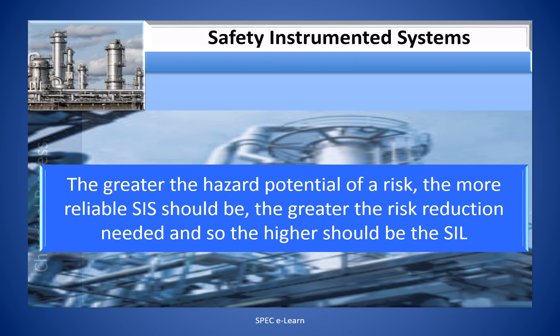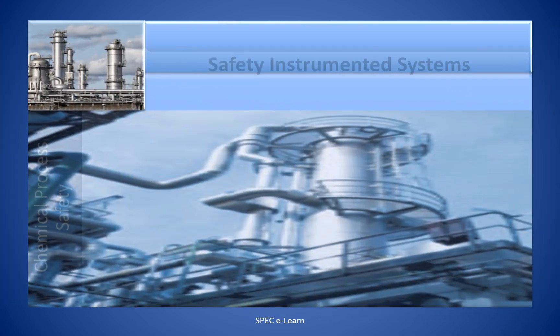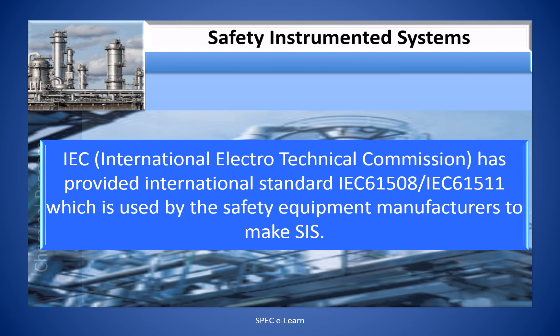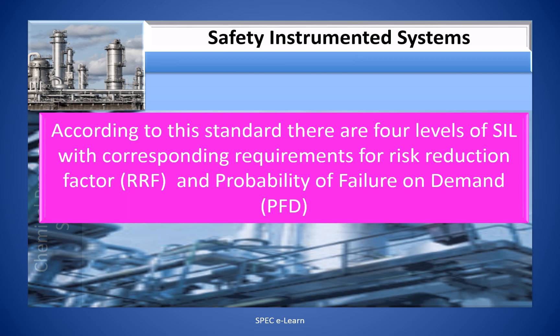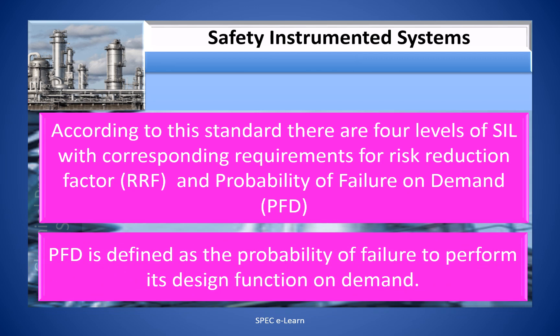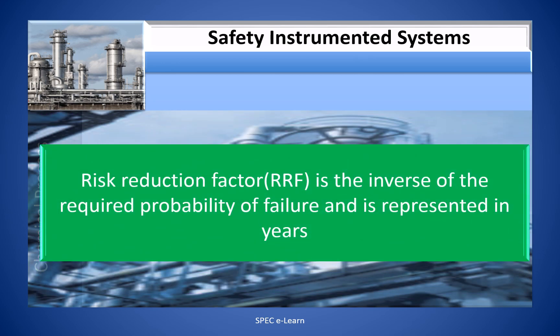The greater the hazard potential of the risk, the more reliable the SIS should be. The greater the risk reduction needed, the higher the SIL required. IEC — the International Electrotechnical Commission — has provided international standards IEC 61508 and IEC 61511, which are used by safety equipment manufacturers to design SIS. According to this standard, there are four levels of SIL. The Risk Reduction Factor, RRF, and Probability of Failure on Demand, PFD, are defined — where PFD is the probability of failure to perform its design function on demand, and RRF is the inverse of PFD, represented in years.